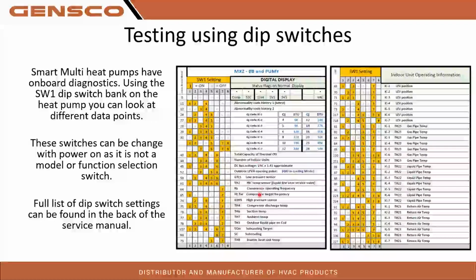Like I said, with the smart multi dip switches, there's a lot of stuff that you can look at. Individual coil temperatures, pressures, compressor speed, subcooling targets, discharge temperatures, all kinds of stuff. These are in our book here. You guys can take screenshots of this too if you want. But these are some of the most common ones that we use. If you look in the back of your smart multi-service manual, there are pages of different switch settings that you can use to look at different values.